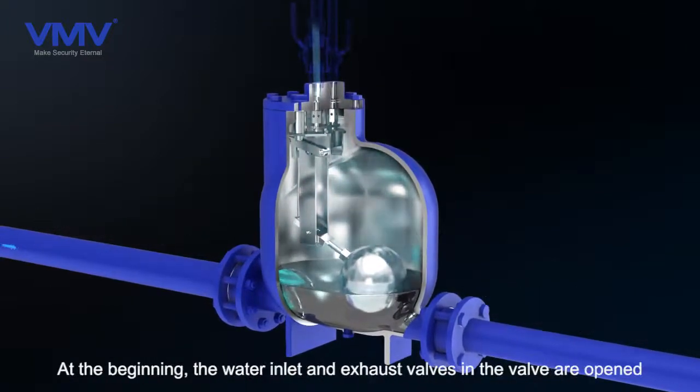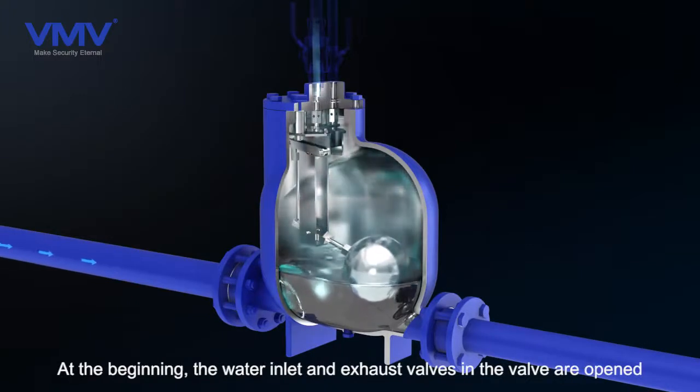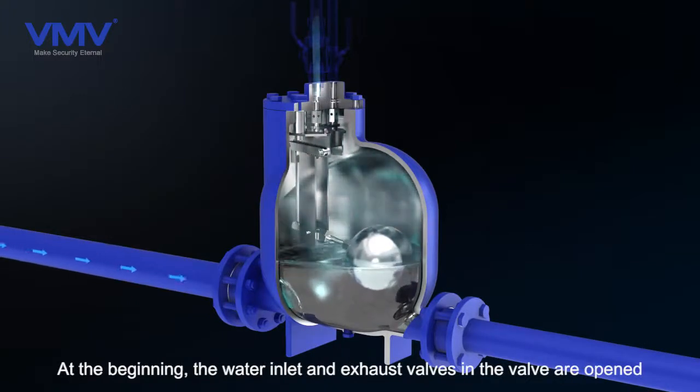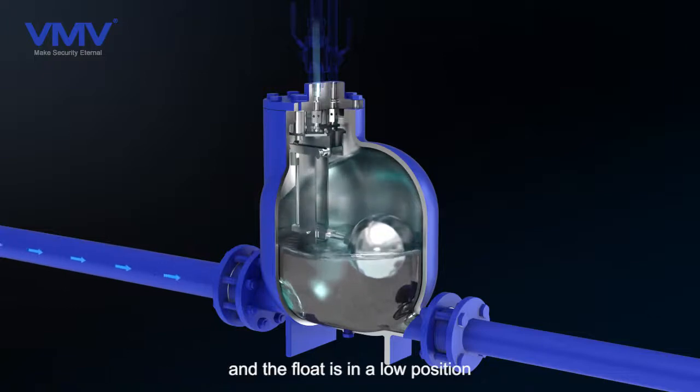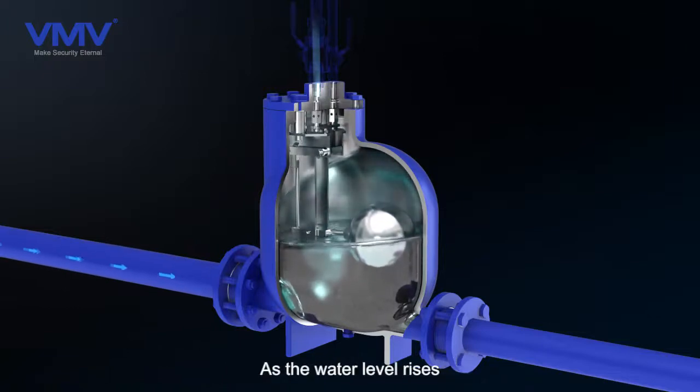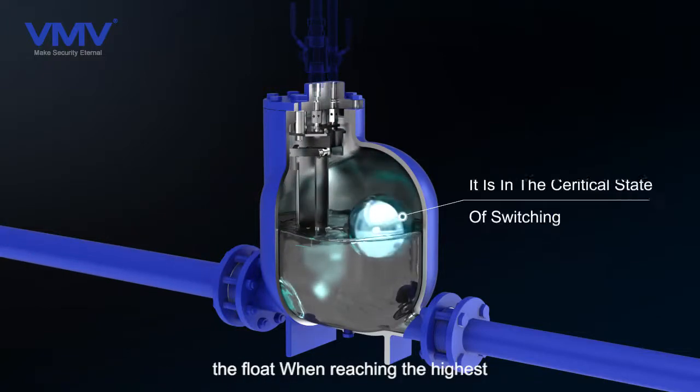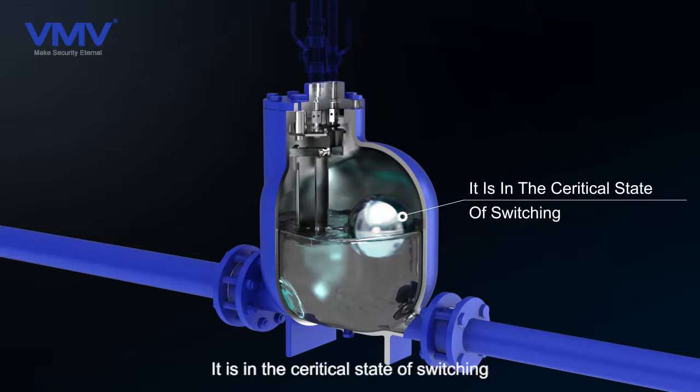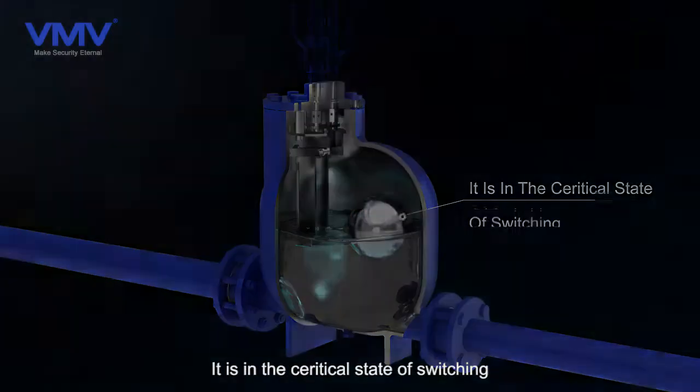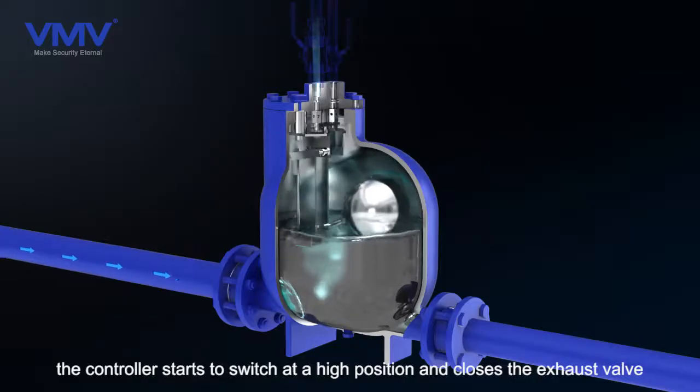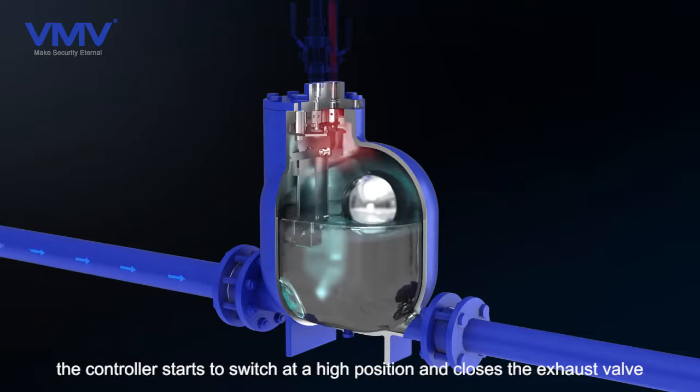At the beginning, the water inlet and exhaust valves in the valve are open, and the float is in a low position. As the water level rises, the float reaches the highest position, reaching the critical state of switching inlet steam and drainage. The controller starts to switch at this high position.